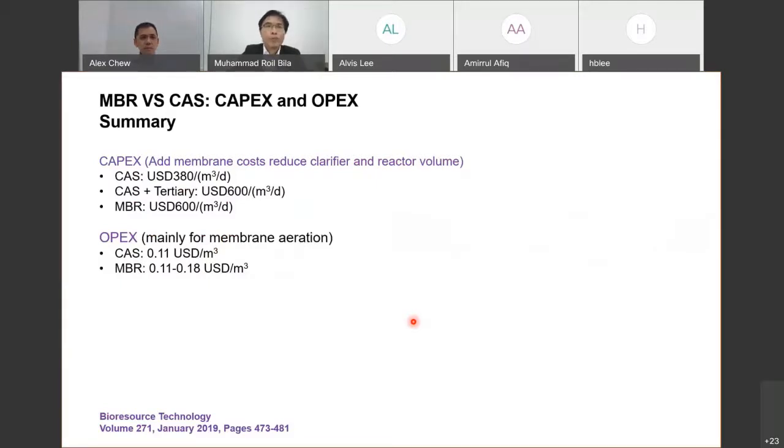If you compare the investment cost of conventional activated sludge, on average, this is data from a Chinese report, the investment is about 380 USD per cubic meter per day capacity. If you have conventional activated sludge with tertiary treatments, with UV, activated carbon, and so on, the investment cost is close to USD 600.